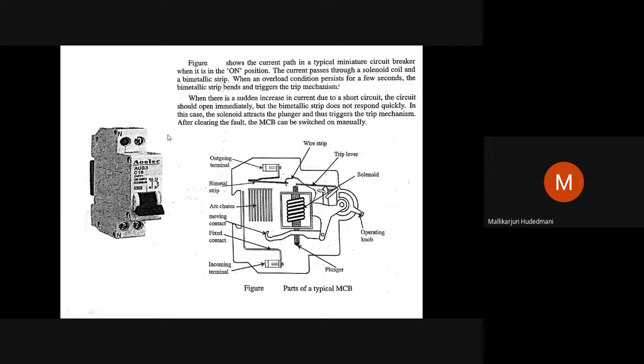So this is a commercially available product shape. This is called two pole. We have two screws here. You can connect two wires and you can take two wires out of this. It means it is a two pole MCB. If I have only one connection possibility, one connection drawn, it is one pole, single pole; then two pole, three pole, like that. Multiple control points are available. That name is given like that.